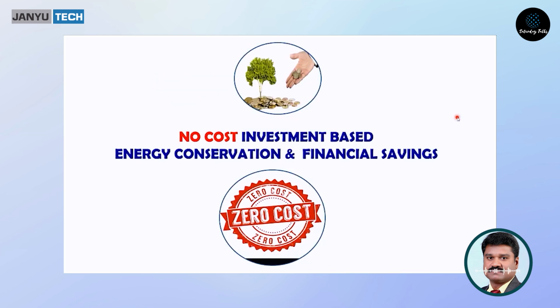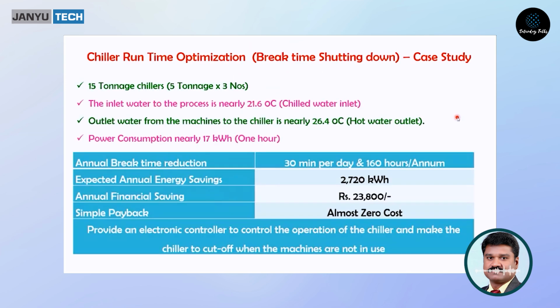Let me give some examples of low-cost and cost-investment-based proposals from a case study. This is a recent case study we did in Chennai, for a company manufacturing pressure cooker gaskets. They have a 15-ton chiller, 5-ton into 3 units, normally running from 9 AM to 7 PM, with two intermittent breaks - one for morning breakfast and one for afternoon lunch. The inlet water temperature is around 21 to 22 degrees, and the outlet temperature from the machine is normally 26 to 27 degrees.